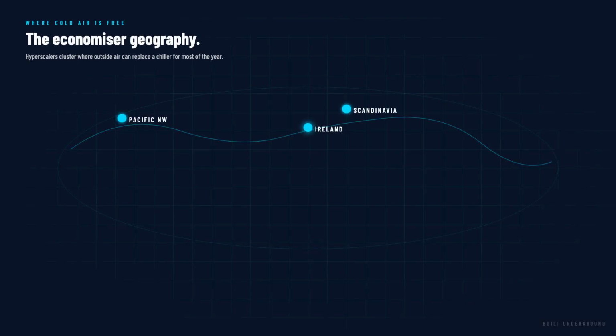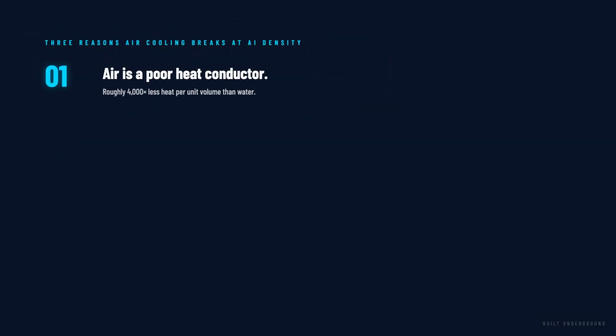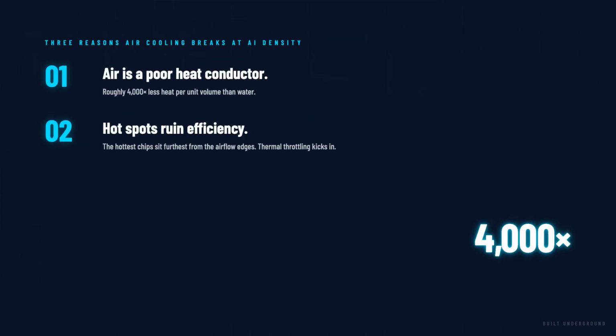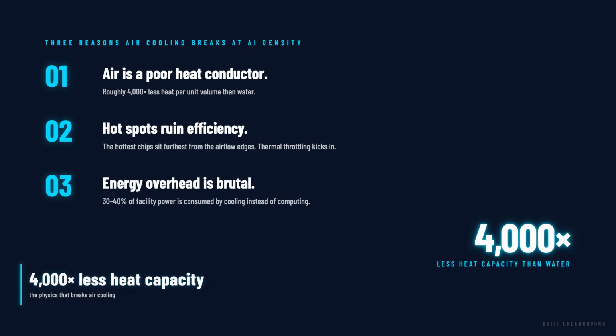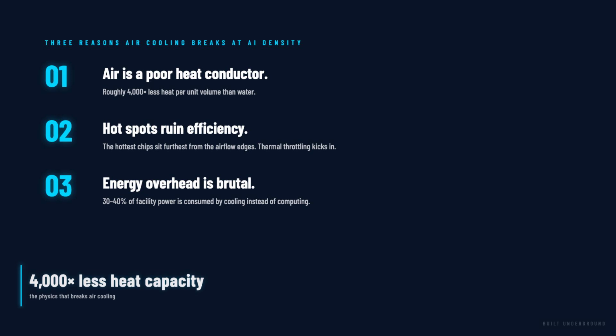Air cooling works. It has worked for decades, and for standard enterprise workloads running at 5 to 15 kilowatts per rack, it is still perfectly adequate. But it has three fundamental limitations. One, air is a poor heat conductor. It carries roughly 4,000 times less heat per unit volume than water.